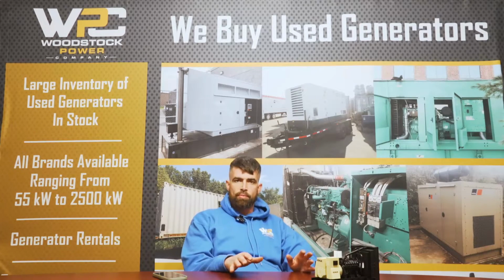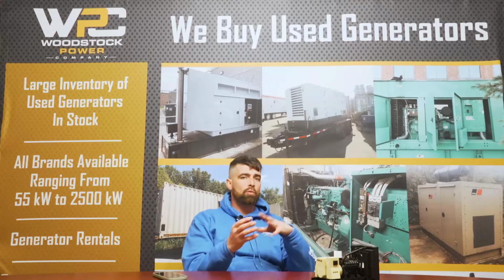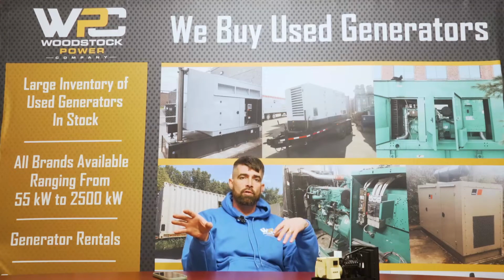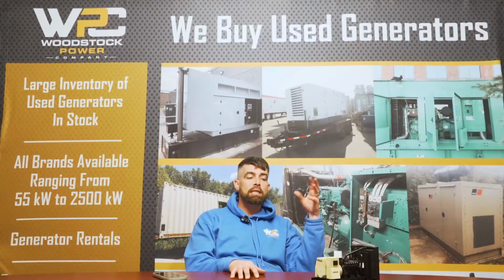If you have any questions about where you're allowed to put water and what chemicals to use, we'll do another video on that as well. But the main point that I want to make is that anything that should not belong in the generator or near the generator should not be there. You can always inspect for any mice and squirrels or any other insects that possibly can get inside of the generator and chew up some wires. You can check for any leaks that you see that weren't there before.